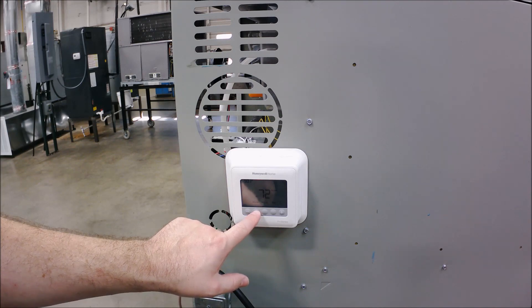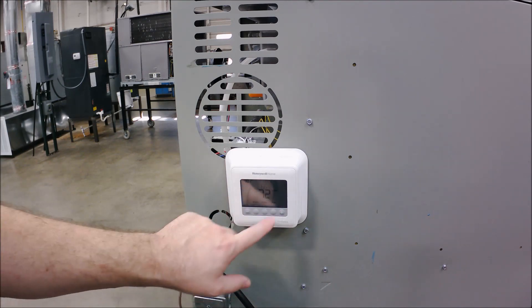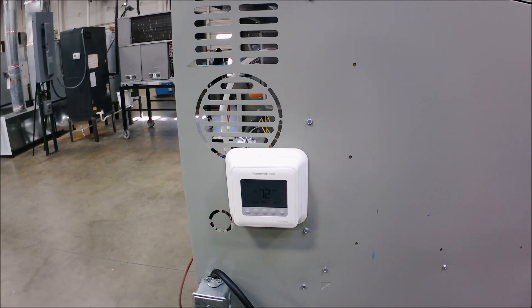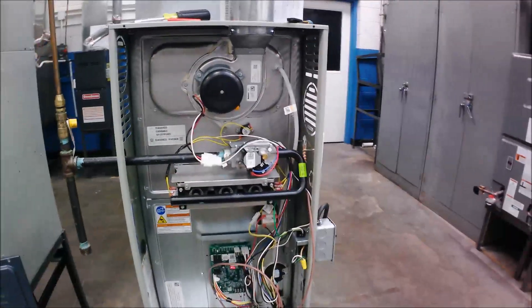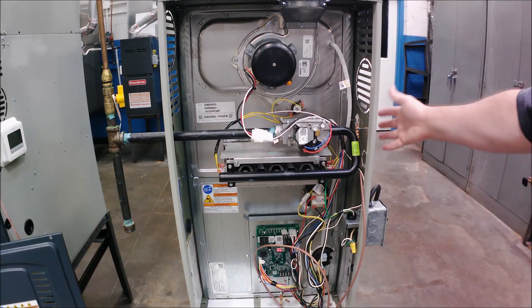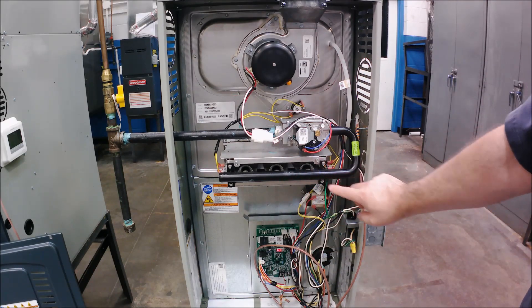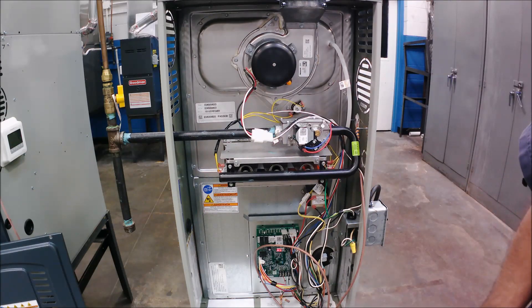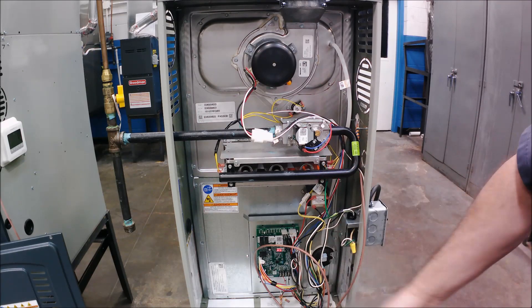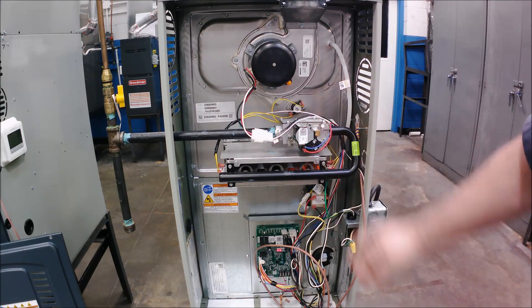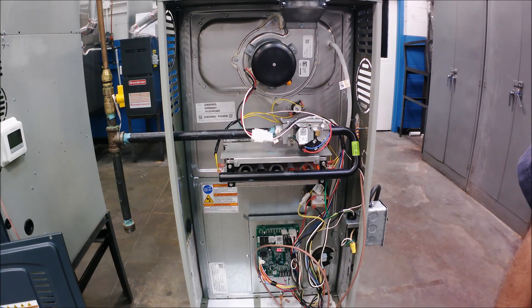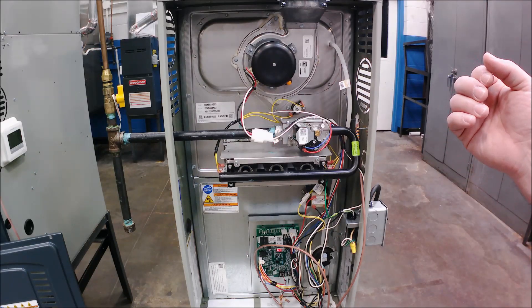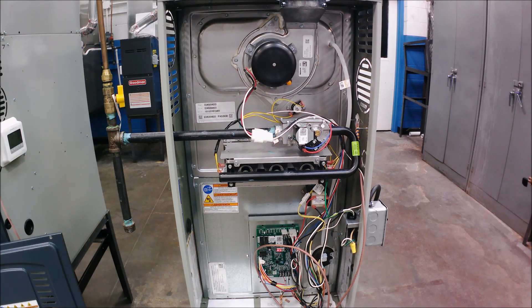We would turn the heat on. The heat is set to 66, so I'll raise it above room set point. Thermostat calls for heat, inducer motor is on, pressure switch closes, hot surface igniter starts to glow and gets up to temperature. I've turned the gas on. Once it gets up to temperature, the timing in the board will energize the gas valve with that signal from W, opening the valve, letting gas through, and lighting. There she goes! In about 30 seconds the heat exchanger will warm up and the circuit board will turn on the blower, blowing warm air into our ductwork.